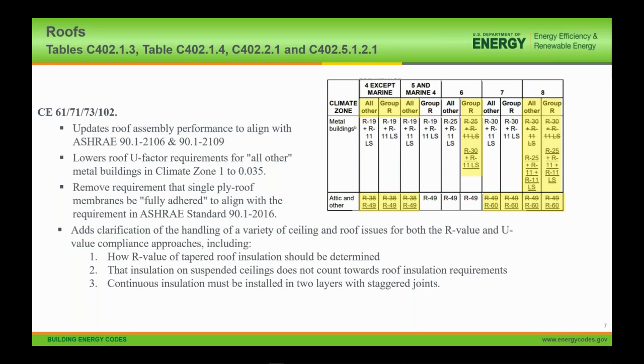The requirement that single-ply membranes be fully adhered was removed, expanding the range of products that comply with the IECC requirements. And then there was new language that further clarified how roof insulation needed to be installed, including clarity on the calculation of tapered roof insulation and how to calculate the R-value, making it clear that insulation on suspended ceilings doesn't count towards roof insulation requirements, and then requiring that continuous insulation be installed in at least 2 layers with staggered joints.